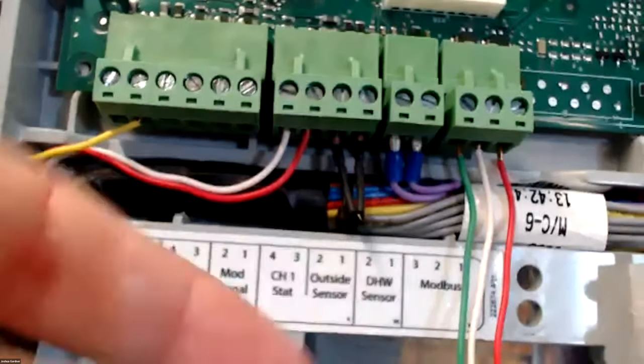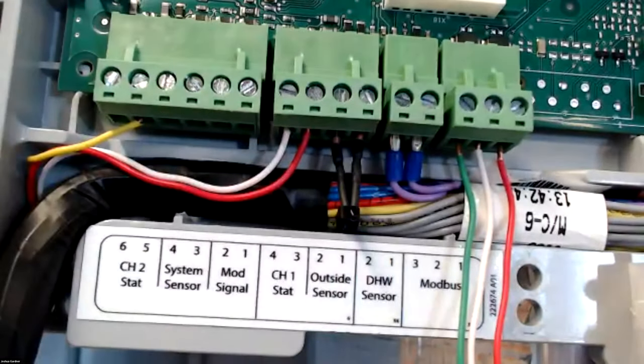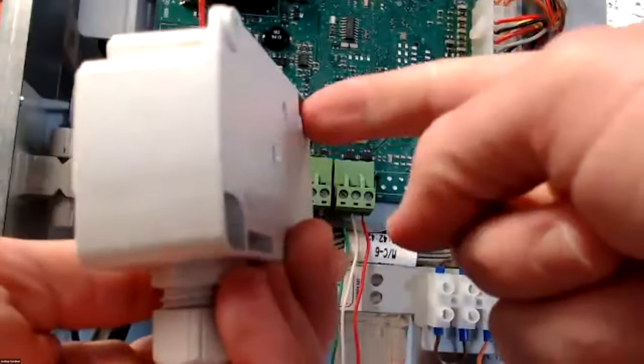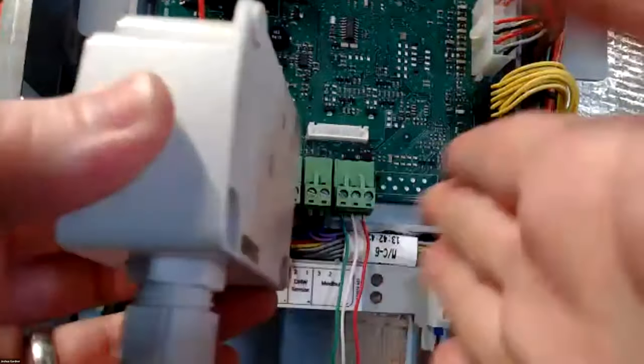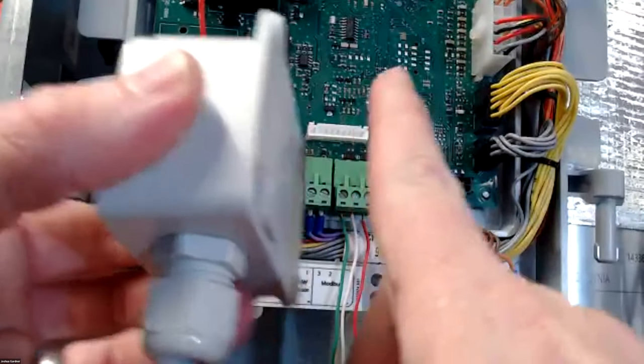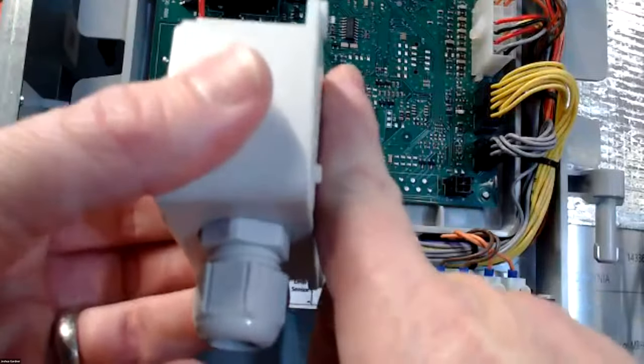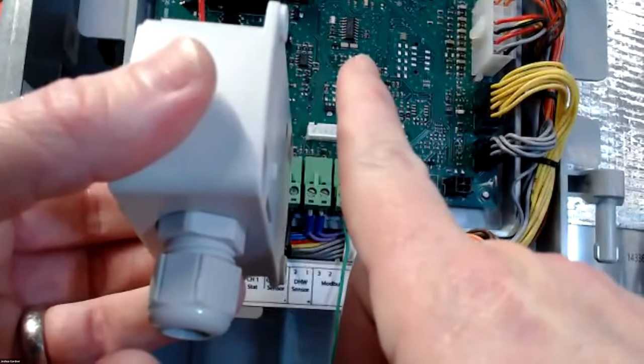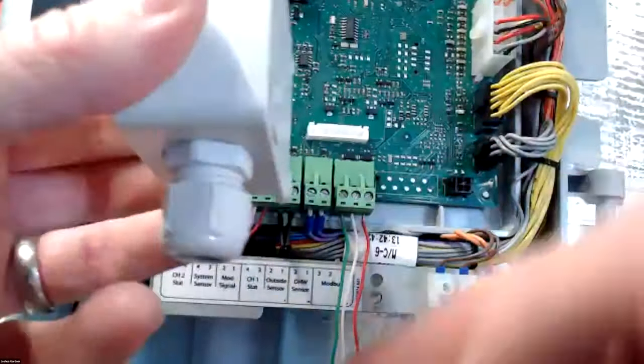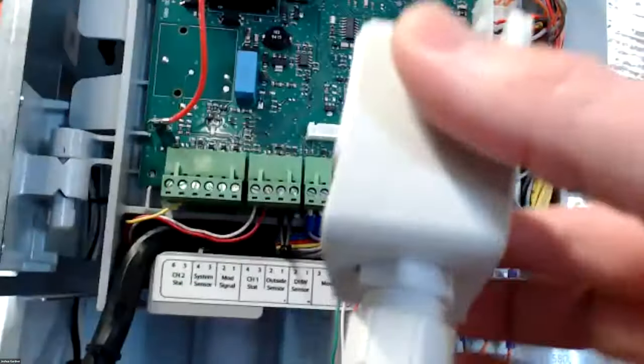Next one is our outdoor sensor. I put the actual outdoor sensor in here for training purposes. But again, it's gonna be this module right here that you're gonna mount outside. The outdoor sensor does come with a little metal bracket that goes along back here. It actually stands the outdoor sensor, so it's actually off the wall. So this outdoor sensor doesn't actually mount right up against the wall. It sets it off about 3/4 of an inch. That way you get good airflow around here and you can get a true temperature on the outside.